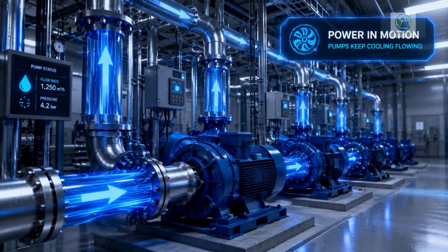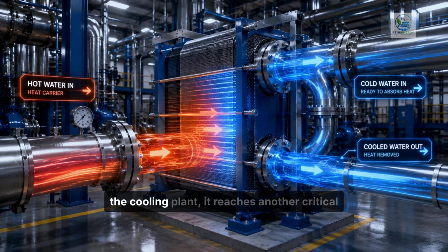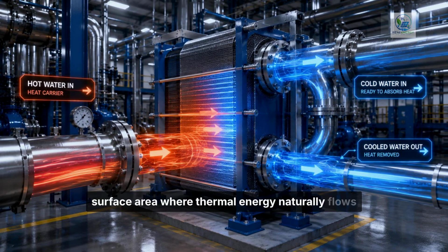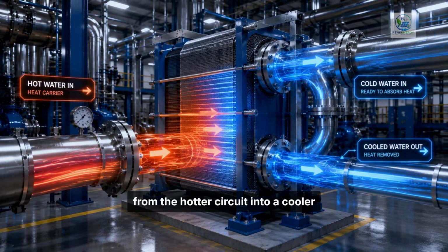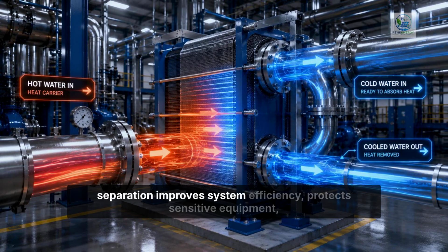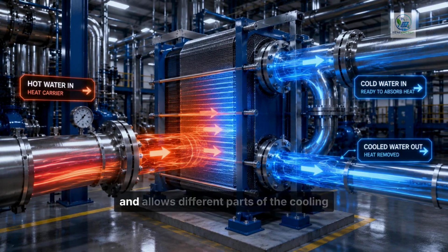away from the processors. As the warmed water flows deeper into the cooling plant, it reaches another critical piece of equipment: the heat exchanger. Its purpose is simple but essential: transfer heat from one water loop to another without allowing the two water supplies to mix. Thin metal plates or tubes create a large surface area where thermal energy naturally flows from the hotter circuit into a cooler one. This separation improves system efficiency, protects sensitive equipment, and allows different parts of the cooling network to operate under their own optimized pressures, temperatures, and water chemistry. The heat itself continues its journey, moving from one loop to the next while the water remains isolated.